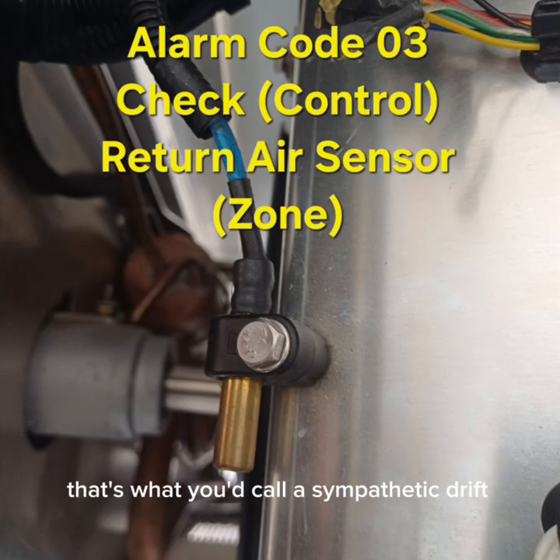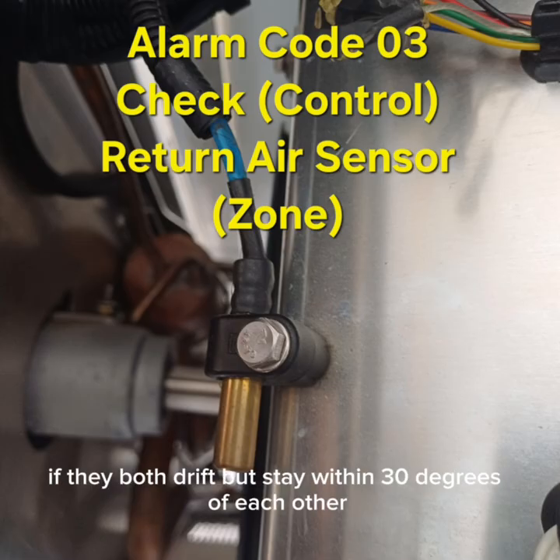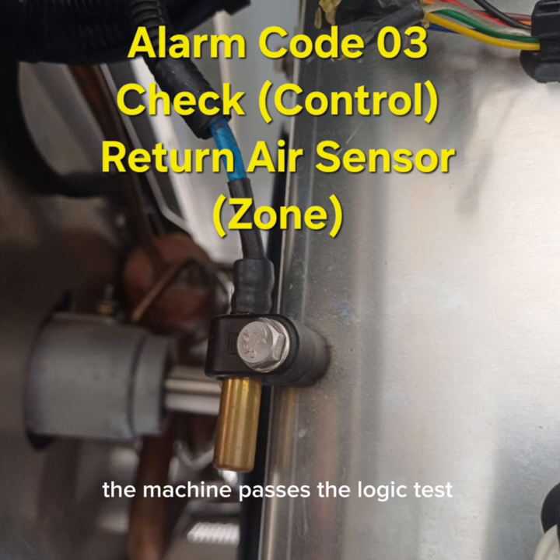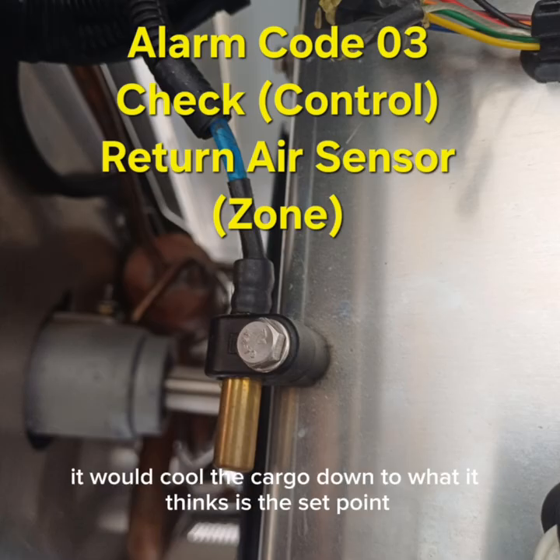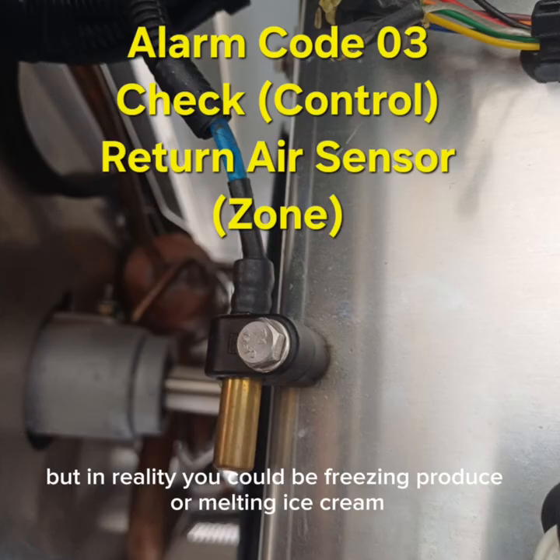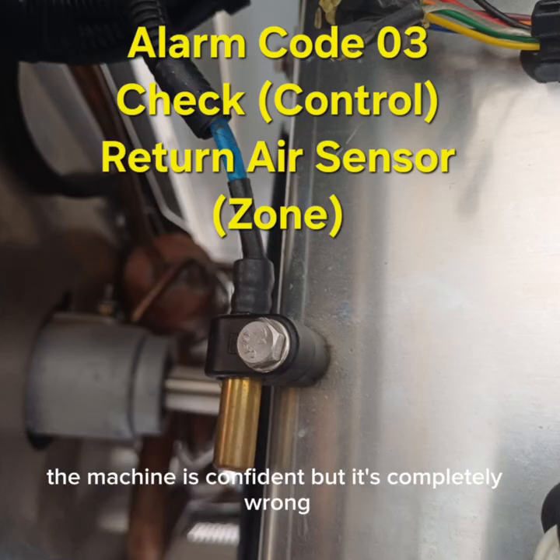That's what you'd call a sympathetic drift. If they both drift but stay within 30 degrees of each other, the machine passes the logic test. It thinks everything is fine, but it's hallucinating. At that point, the machine has no idea it's wrong. It would cool the cargo down to what it thinks is the set point. But in reality, you could be freezing produce or melting ice cream. The machine is confident, but it's completely wrong.